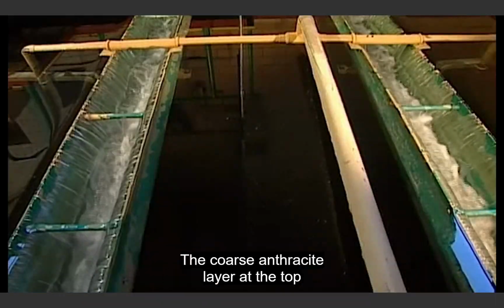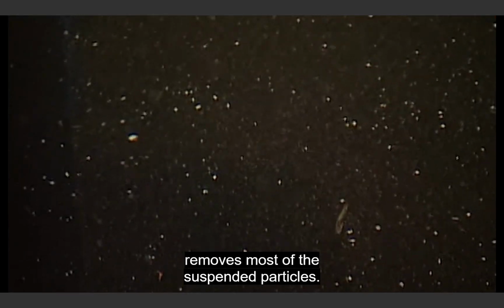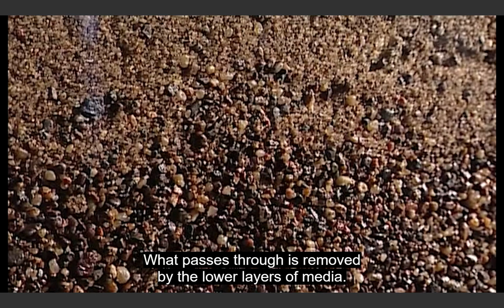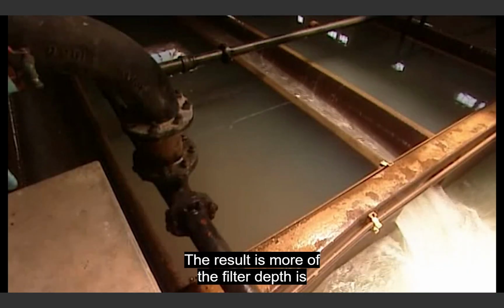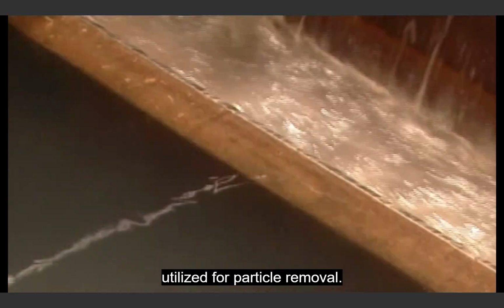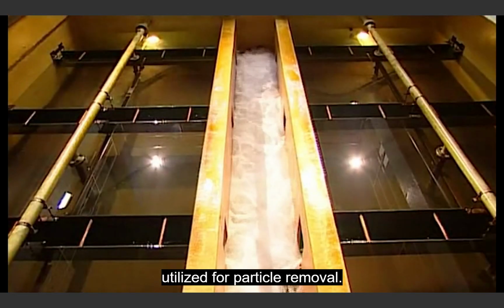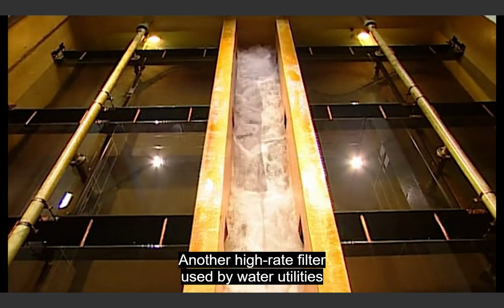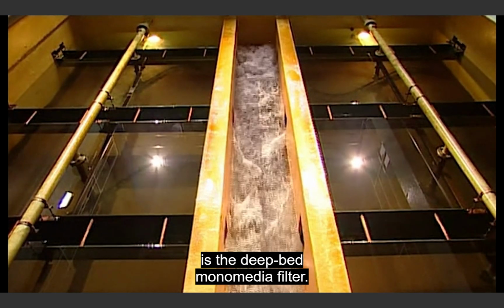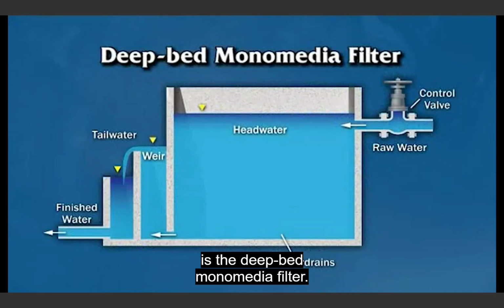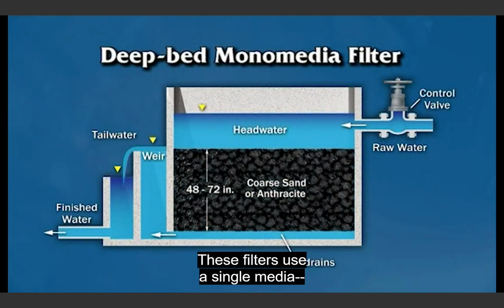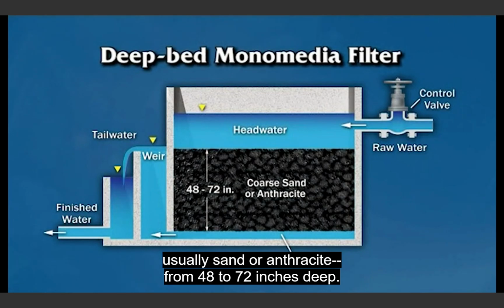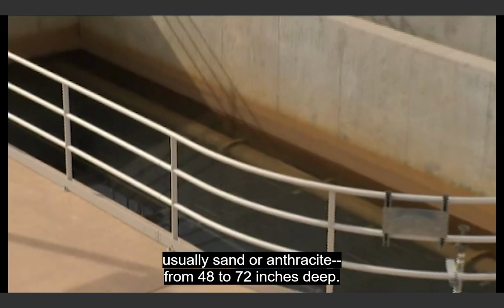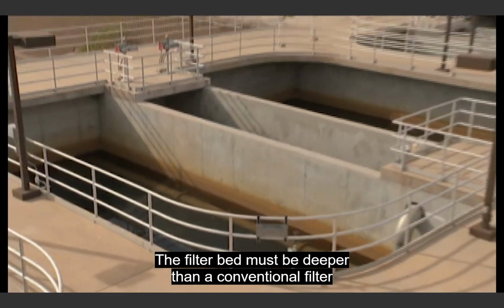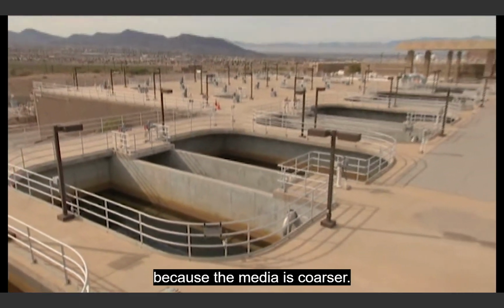The coarse anthracite layer at the top removes most of the suspended particles. What passes through is removed by the lower layers of media. The result is more of the filter depth is utilized for particle removal. Another high-rate filter used by water utilities is the deep bed monomedia filter. These filters use a single media, usually sand or anthracite, from 48 to 72 inches deep. The filter bed must be deeper than a conventional filter because the media is coarser.